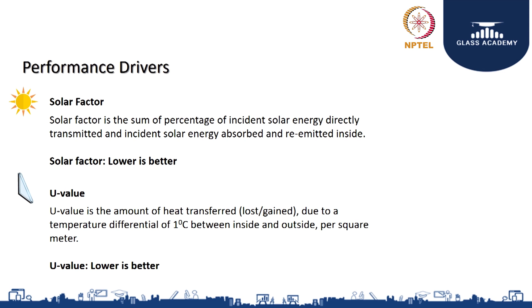So for a condition, say outside is at 40 to 45 degrees and inside my set temperature is around 25 to 26 degrees, there is a possibility of a delta T difference of about 15 to 20 degrees. So the outside temperature is absorbed by the glass and transmitted inside, multiplied by 20, because for every 1 degree there is a transfer of 5.7 watts. So 5.7 into 20 will be the amount of heat transferred through indirect heat.